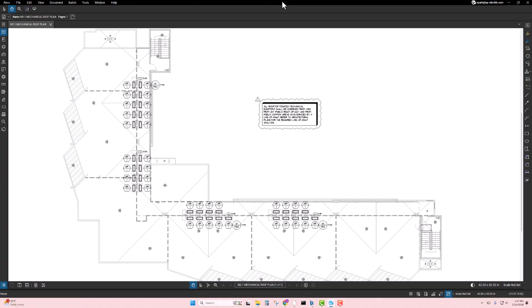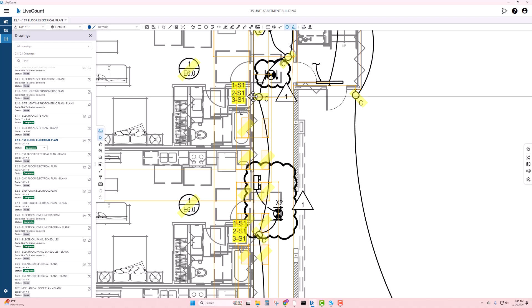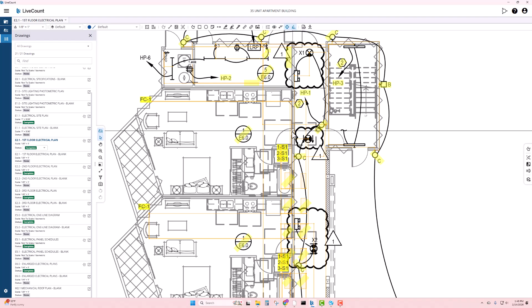So what I did is I took the locations of these heat pumps and I correlated them with each unit, and I ran 12 wire up to the heat pump and then 12 wire back down to the fan coil, because those condensing units feed the fan coil on the inside of the unit. And so that's why it's a little convoluted here, but I just marked those up. That's something you got to watch out for. If you don't include that stuff, you got to make sure the electricals and the mechanicals are coordinated.